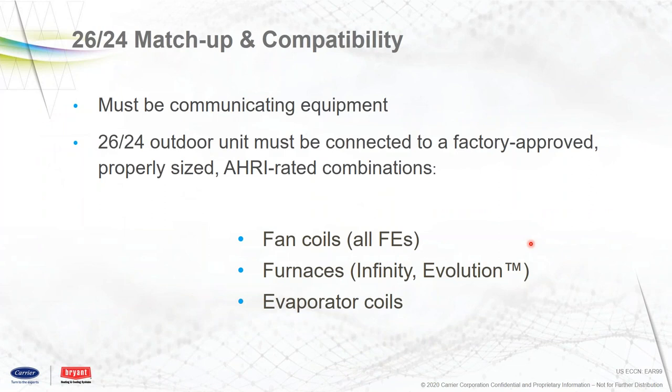As far as matchup and compatibility, the evaporator coils will have an AHRI-rated combination, which isn't going to be any different than what you're doing today with the VNA Zeros or the 180s or 280s on the Bryant side. The indoor unit has to be a communicating style indoor unit. If you're doing fan coil, it's got to be the FE, and it's got to be a communicating furnace — Infinity Evolution compatible. If not, you simply can't use this. Control-wise it just won't function. It's got to be a communicating indoor unit and the Infinity Connects controller.